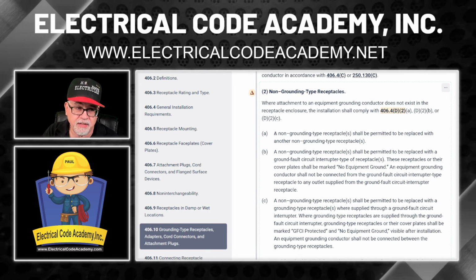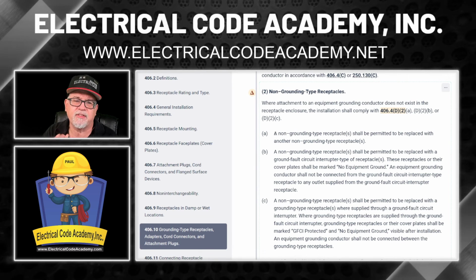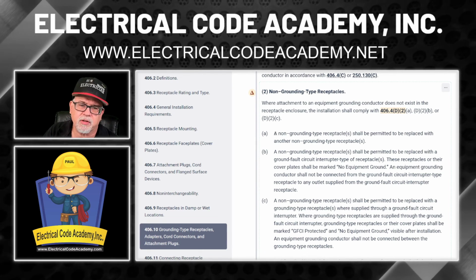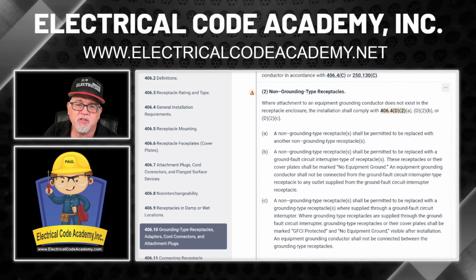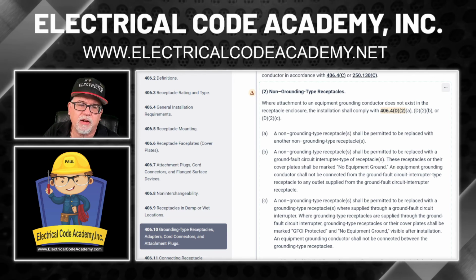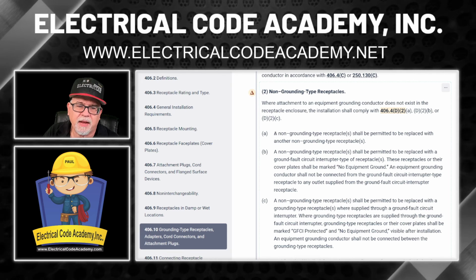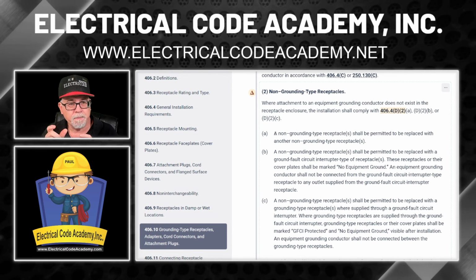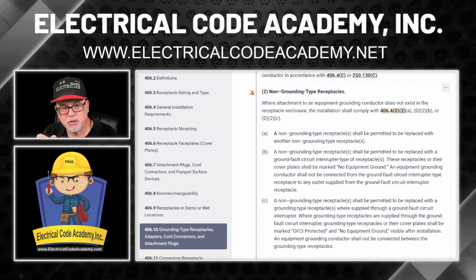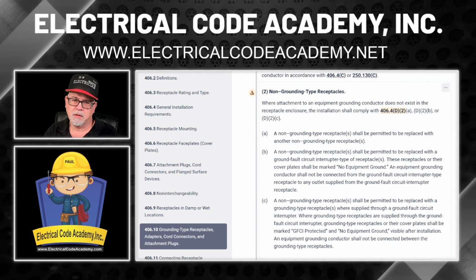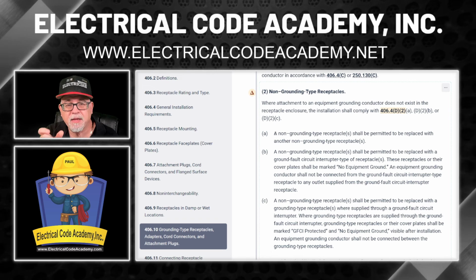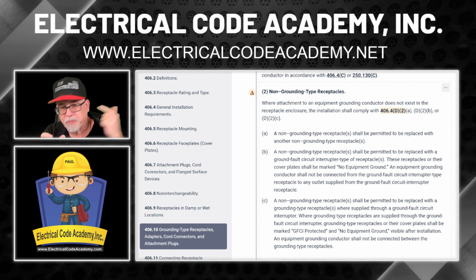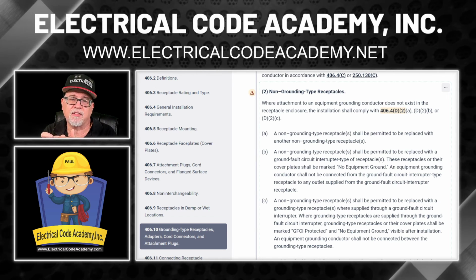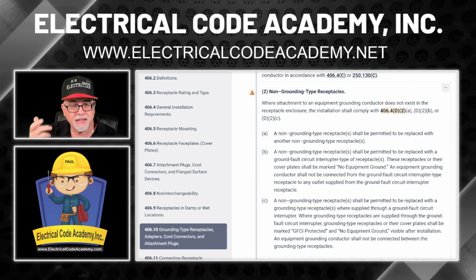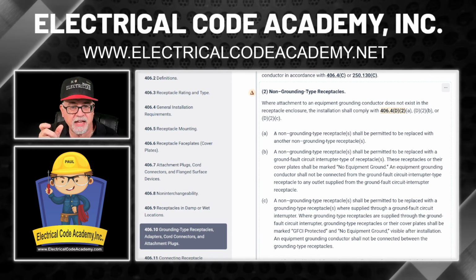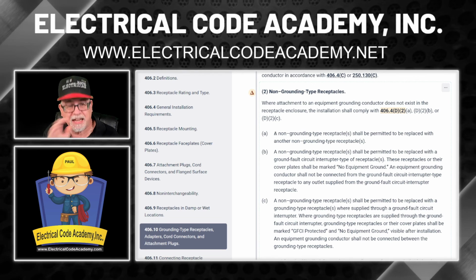So the little difference in this one is, let me read it to you. We're at C now. It says, a non-grounding type receptacle, kind of what was there, the two prongs, shall be permitted to be replaced with a grounding type receptacle where supplied through a ground fault circuit interrupter. So when it says supplied through, that means I take the two prong out, I put the three prong grounded type in, and if I have a GFCI circuit breaker, it's protected through that circuit that's supplied from that GFCI circuit breaker. That's what it means, supplied through the GFCI device, okay? So that's what that means.